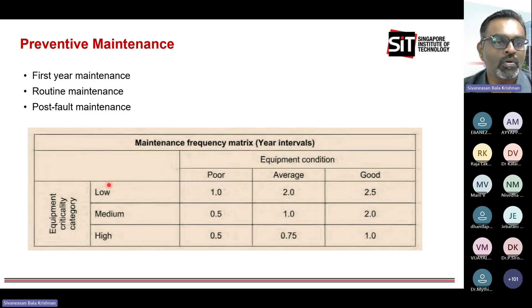If the equipment criticality is very low and the equipment condition is good, you can operate the maintenance interval every 2.5 years, which is quite long. That means the environment is good, the load factor - meaning the utilization of the equipment - is less than 50%, and the age of the equipment is less than 5 years. This is how we categorize 'good'. So it can be monitored every 2.5 years.